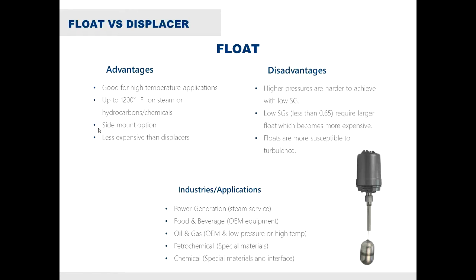The disadvantages of floats are pressure. Higher pressures are sometimes hard to achieve with lower SGs. They can be achieved, but the price will increase dramatically. Low SGs require larger floats, which become more expensive. So the higher the pressure and the lower the SG, the more we have to bulk up that float and chamber, making it a more expensive product. Floats are also more susceptible to turbulence than a displacer would be.